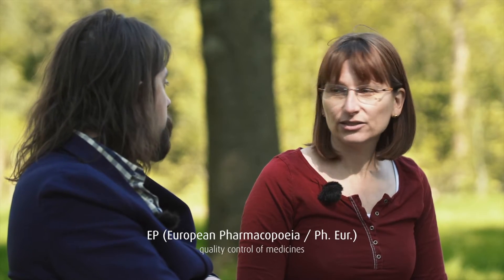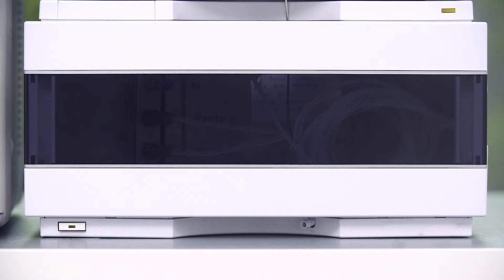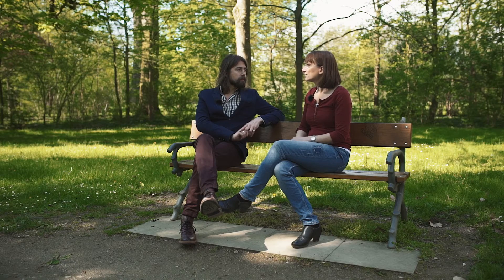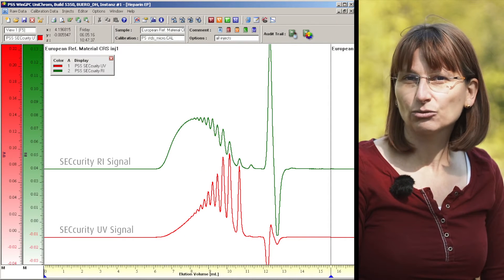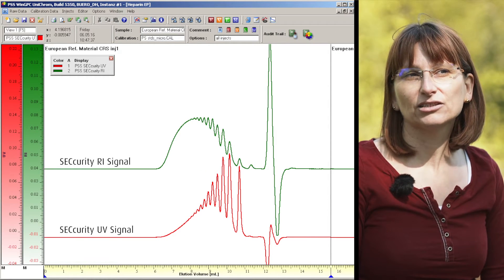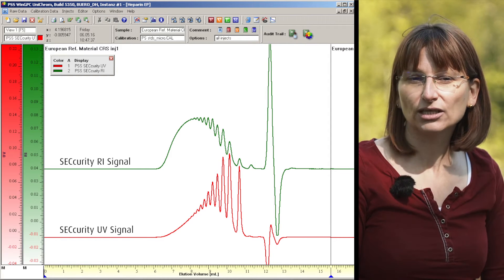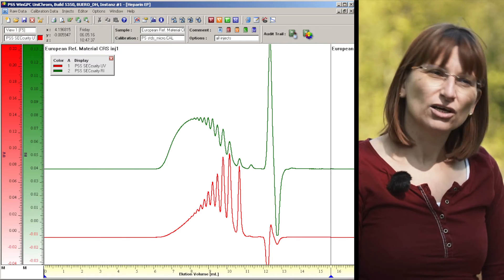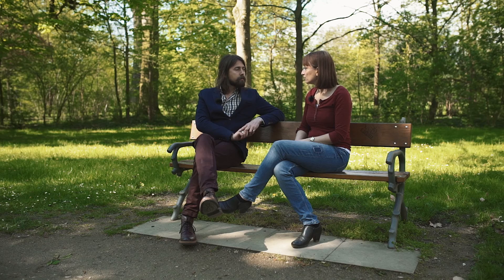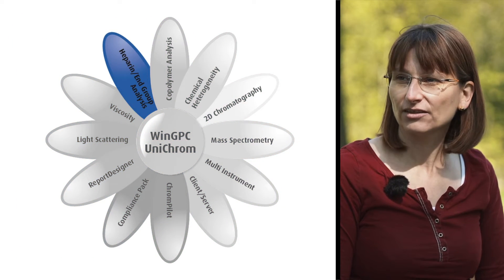For the EP, you need a size exclusion chromatography instrument with two detectors: a refractive index detector and a UV detector. The European Pharmacopoeia uses as reference material a heparin that has been specially modified so that it has a UV-detectable end group. You get a UV trace and an RI trace, and from their differences you can do an end group analysis and construct a calibration curve. There is an equation given for that in the EP, which was a problem for many users — that's where we came in, developing software to automatically calibrate from the UV and RI traces.